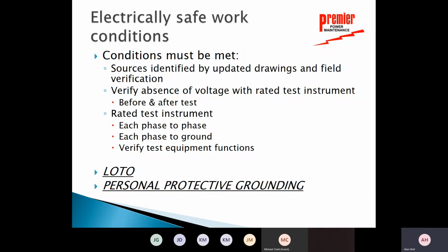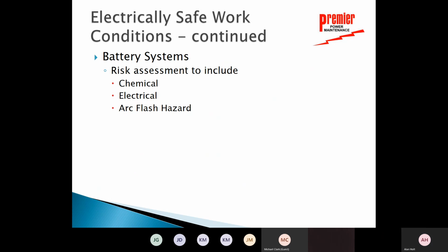Now, Jay, just from your aspect on testing for voltage, I don't believe that we can use electrostatic voltage detectors, even at high voltage. We actually use voltmeters on that as well. Is that correct? Yeah, we have to verify. We are allowed to do it ourselves and check, but they want us to verify then. Okay, yeah. So there is an electrical contact. They're a little different than any place else that we work with regard to that. So there is an actual verification on a voltage reading. They've got voltage meters to actually read that, and it's not just a beeper or buzzer that we deal with. So, okay, we get away from the electrical portion.